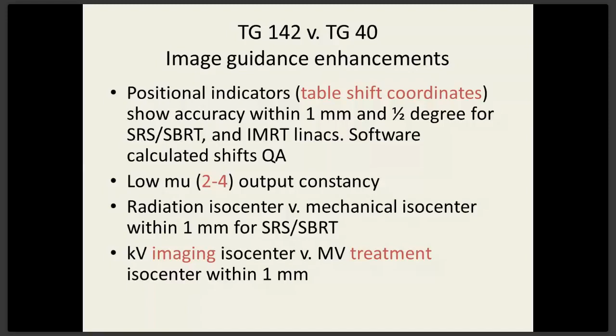Are the ISO centers the same for the KV imager and the MV treatment head? The KV imager has its own ISO center. I know it's connected to the gantry, but it does have its own ISO center. Does the KV imager ISO center match the treatment beam ISO center by 1 millimeter for SRS machines? And here's a quick table that shows some of the differences. If a machine has the ability for cone beam CT and it's used for SRS, it has to be within 1 millimeter.